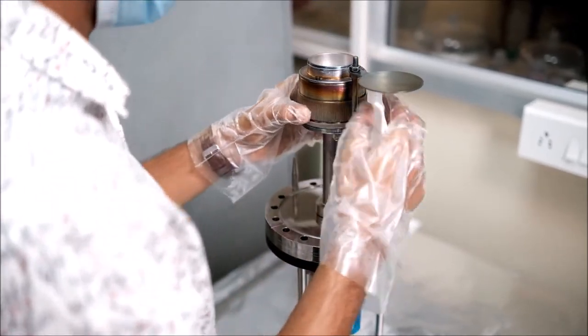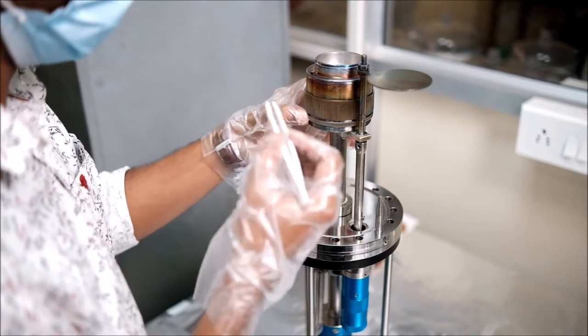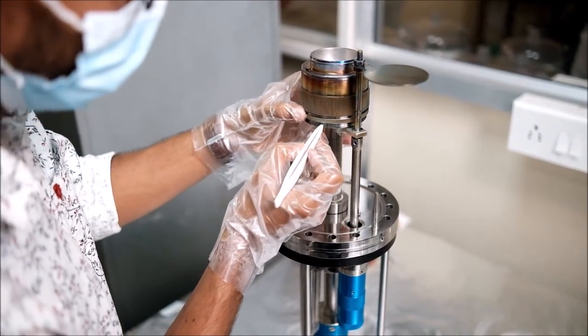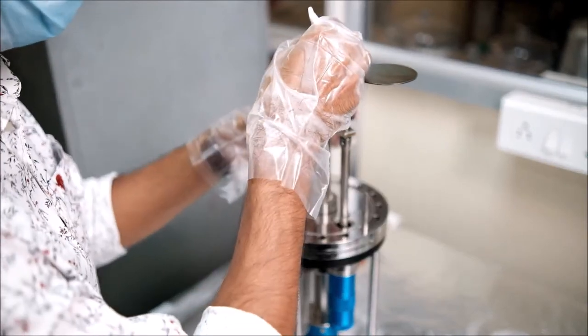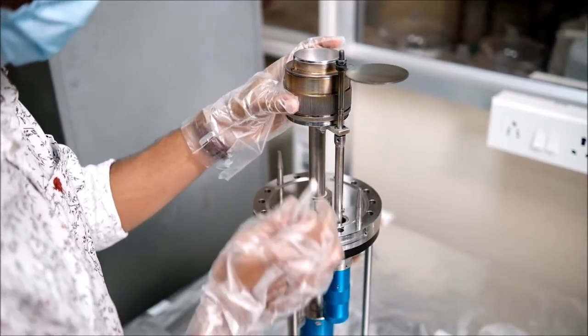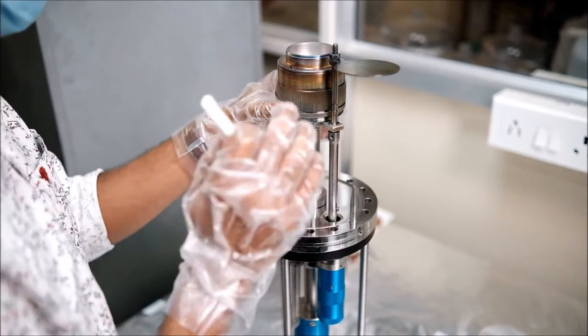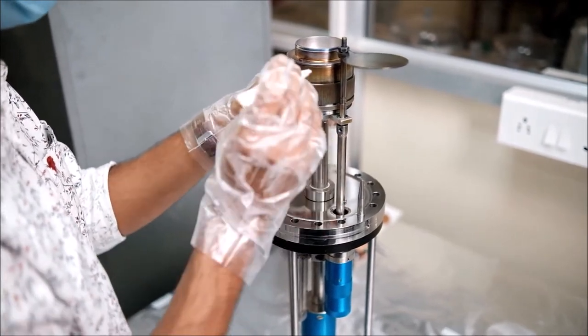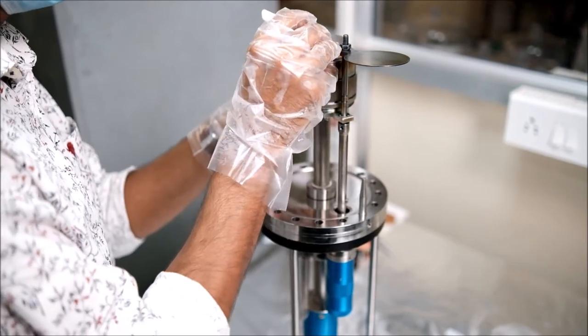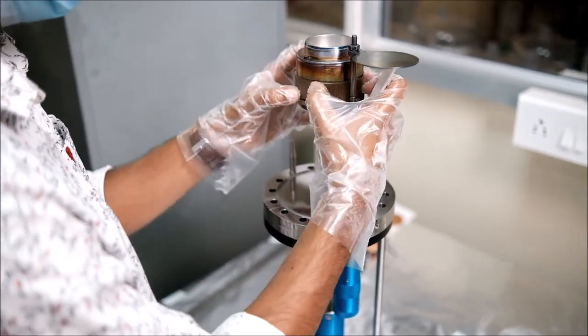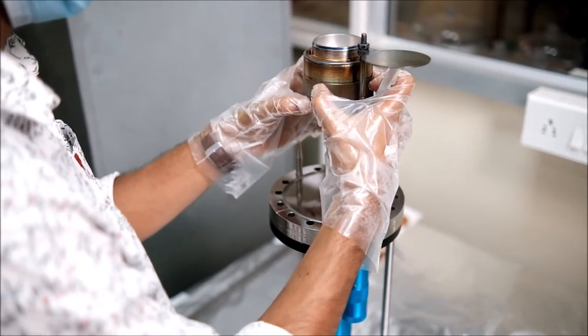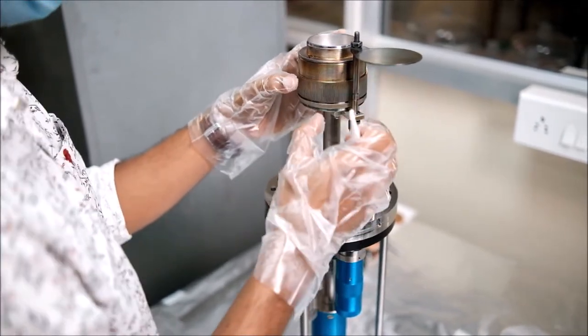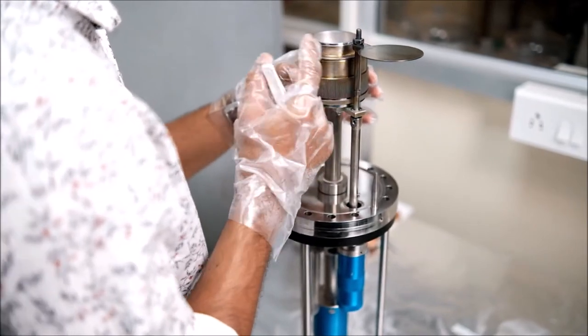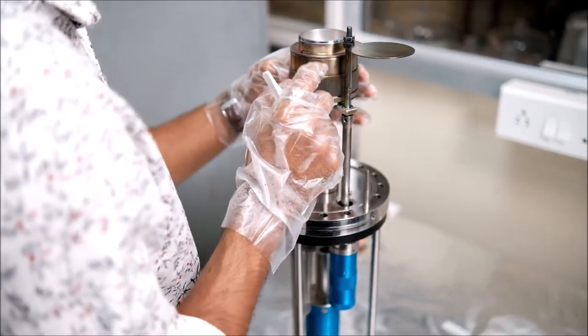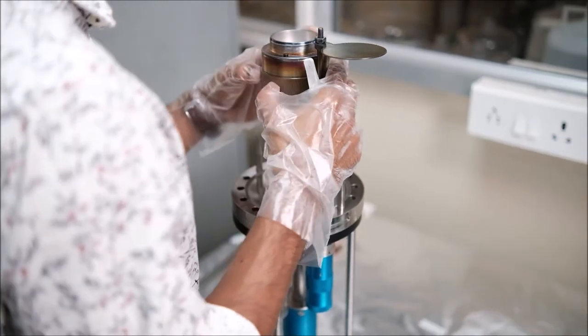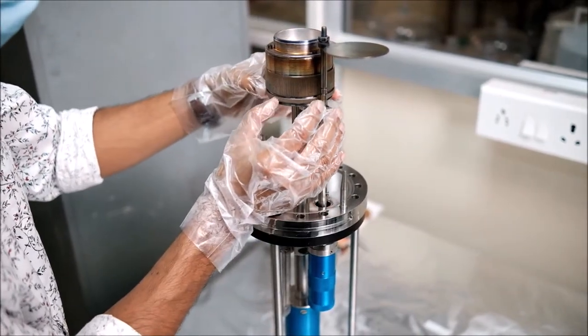So we'll attach it. While attaching it, we have to be careful because the outer part is connected to the ground, and the inner part is connected to the cathode, the power source. So we should not make a short. It is also recommended to keep a 2 mm distance from the target to this part. So first we will make a short connection, and then we will make a half rotation in the opposite direction so that there is a 2 mm distance from the target to this funnel. The half rotation is done. Now with the help of this ring, we will lock it.